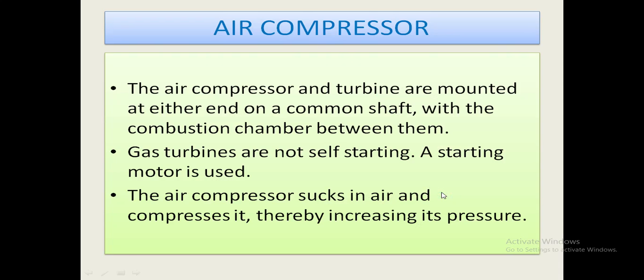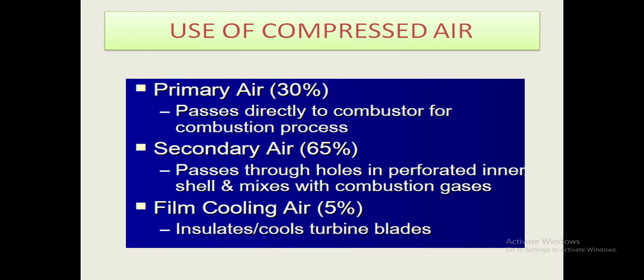Air compressor: the air compressor and turbine are mounted at either end on a common shaft with the combustion chamber between them. Gas turbines are not self-starting, so a starting motor is used. The air compressor sucks in air and compresses it, thereby increasing its pressure. Primary air (30%) passes directly to the combustion process. Secondary air (65%) passes through holes in the perforated inner shell and mixes with combustion gases. Film cooling air (5%) insulates or cools the turbine blades.